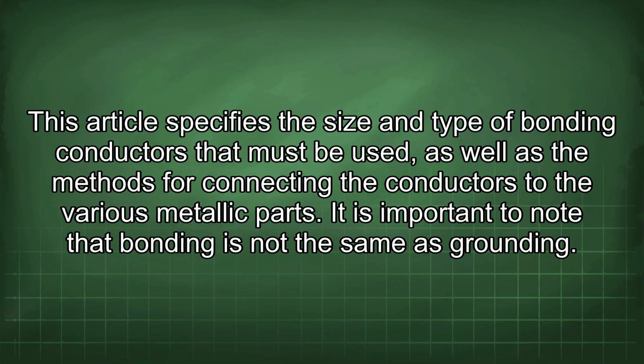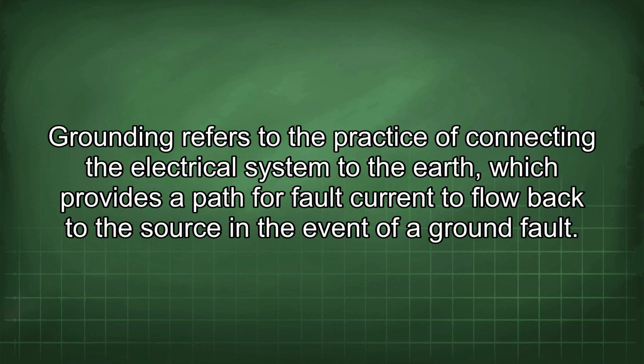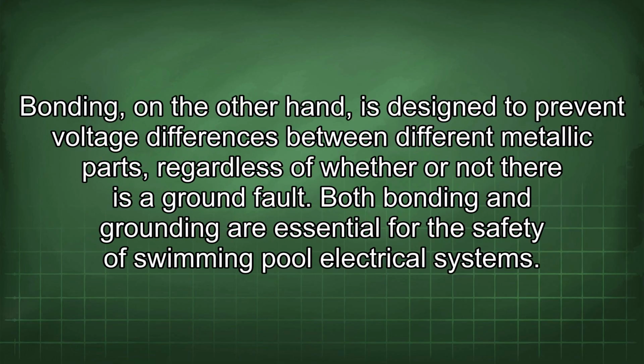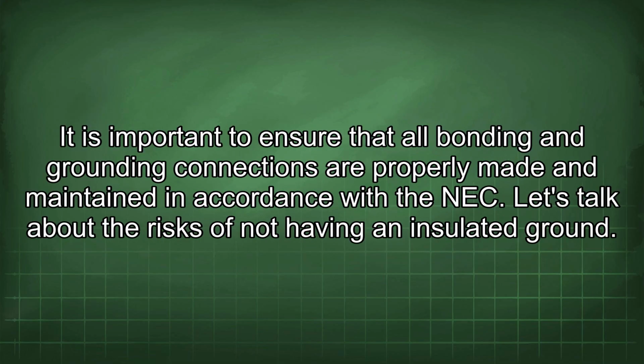It is important to note that bonding is not the same as grounding. Grounding refers to the practice of connecting the electrical system to the earth, which provides a path for fault current to flow back to the source in the event of a ground fault. Bonding, on the other hand, is designed to prevent voltage differences between different metallic parts, regardless of whether or not there is a ground fault. Both bonding and grounding are essential for the safety of swimming pool electrical systems. It is important to ensure that all bonding and grounding connections are properly made and maintained in accordance with the NEC.